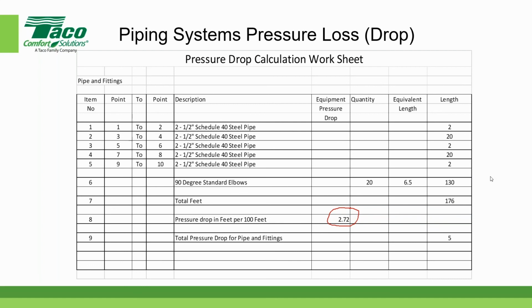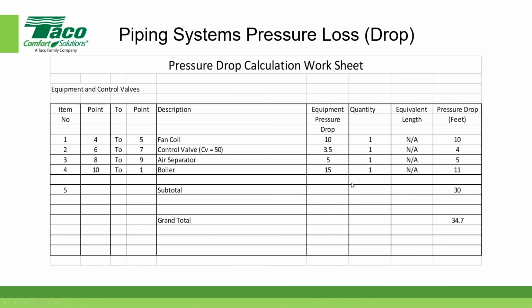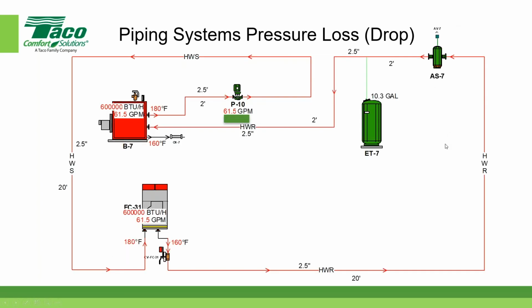And if it was glycol, the equipment manufacturer would have a different value. So when you looked it up in their tables, and you looked up the fan coil, for example, this would be fan coil for water at a specific gravity of 1. But generally speaking, the manufacturers have correction tables, or they have different values for different fluids. So when I looked up the data for the fan coil, it was 10. That was based on water. If it was glycol, I'd have to look deeper into the manufacturer's published data and find out what pressure drop they're publishing for different solutions of glycol. Hopefully that helps. I'm sure it does. Okay.